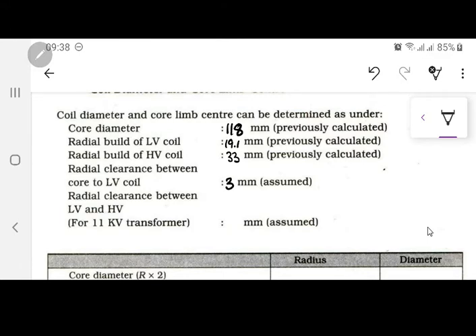This means that the thickness of that cylinder, whatever is used on the step core and on which you are going to do the low voltage winding first, is 3 mm. Now the radial clearance between the low voltage and the high voltage, this parameter is going to be alpha. In this book they call it A, and this distance is very, very critical, because if this A is kept very large, the high voltage is going to be very far apart from the low voltage winding, and this means there is going to be more leakage flux.